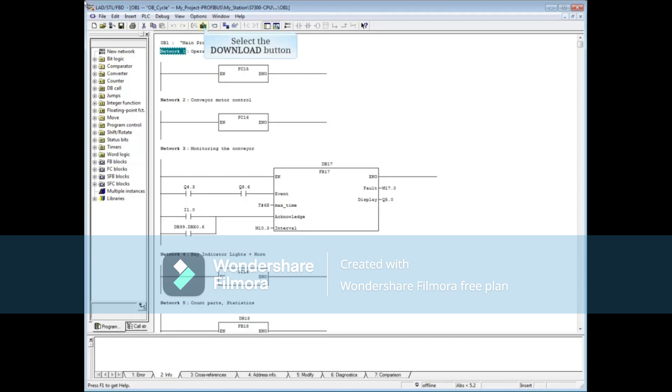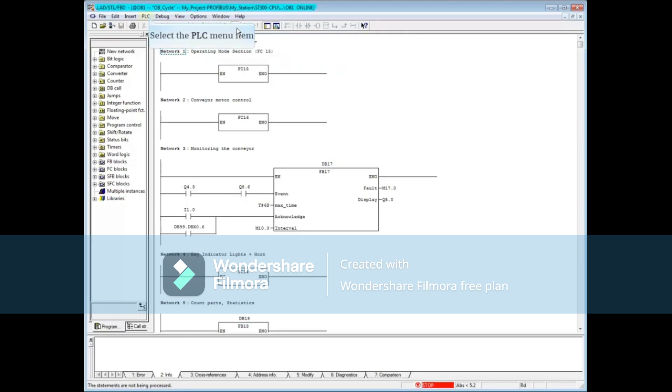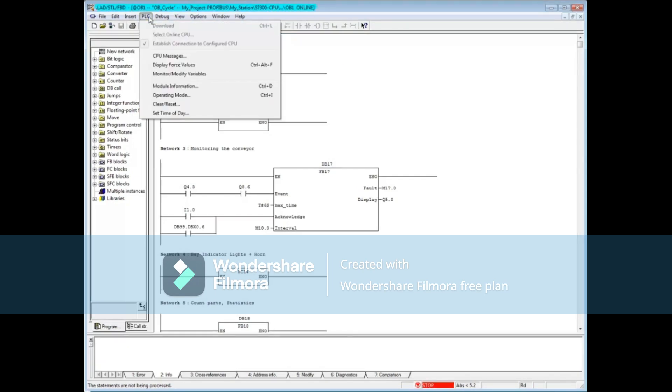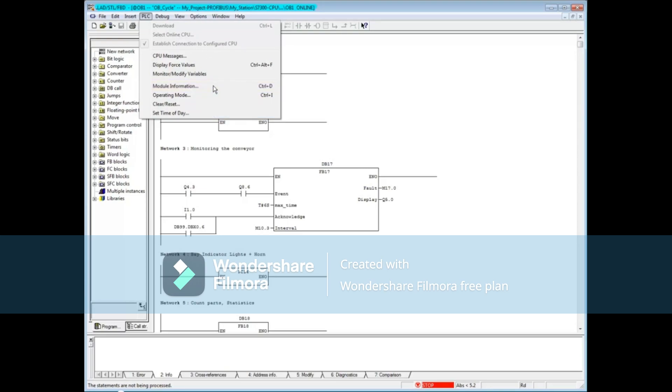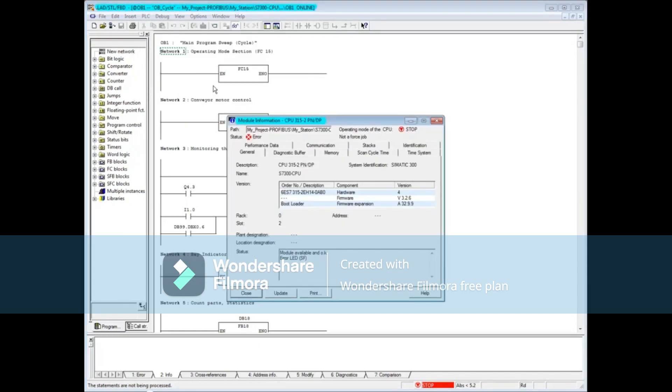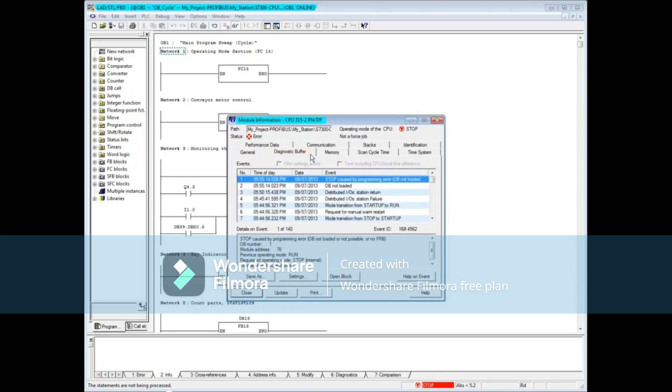To create the fault, we will download OB1 with monitoring on. The PLC has gone to stop mode. Go to the PLC menu and choose module information. Alternatively, you can press and hold the Control key plus the D key.